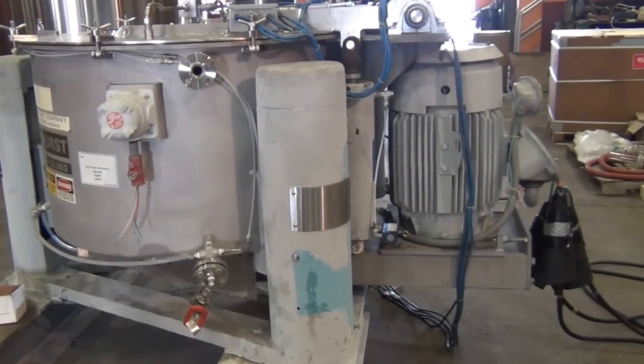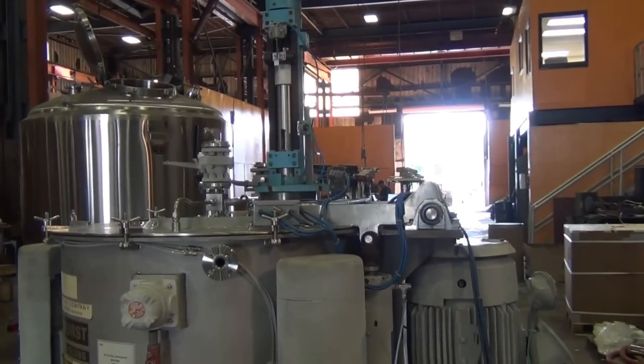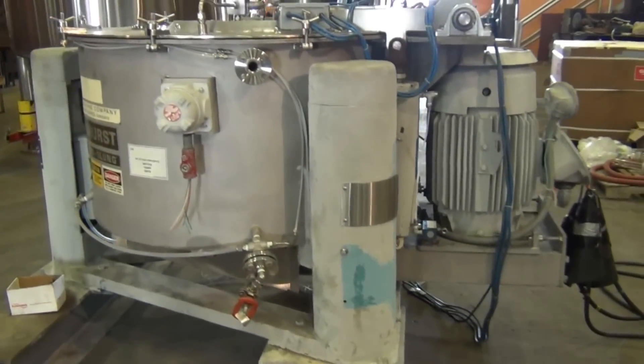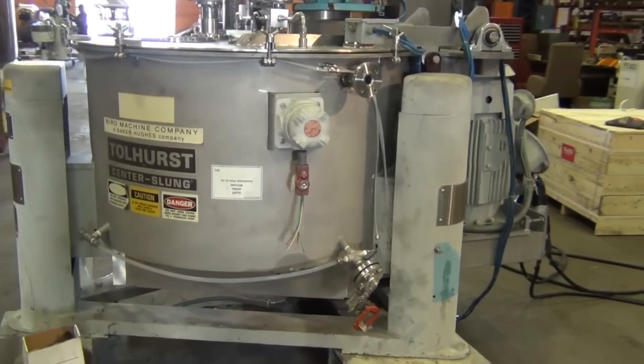This video shows how we use a non-contact tachometer to test the RPMs of a used centrifuge. The machine is a Tolhurst 40 inch by 24 inch basket centrifuge — think of a large washing machine stuck on the spin cycle.